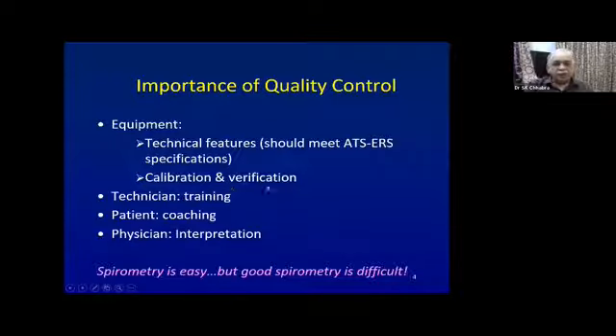Then how to maintain the equipment is important. Every day before the testing is done, the machine has to be calibrated. And the calibration has to be verified during the day, because calibration can easily go wrong. And once calibration is wrong, then the results are wrong. If the calibration is inaccurate, then you might be measuring a vital capacity of 2 liters as 2.5 liters. The technician has to be very well trained, both in the calibration and maintenance of the equipment, as well as to teach the patient how to do the maneuver.